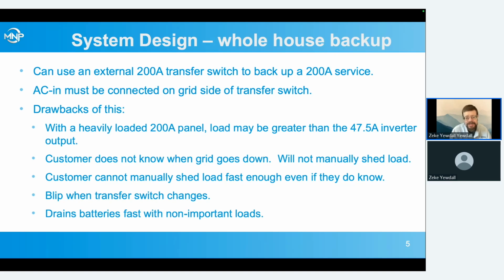But then the issue is the customer doesn't know when the grid goes down. A lot of them will say, I'll just manually shed my heavy loads if the grid goes down, so I'll turn off the air conditioner and the jacuzzi. But if you've got whole house backup, they don't know that the grid went down. I mean, yeah, they can go look at the lights on the inverter or pull up their app, but they don't get a notification like, oh, all of a sudden the lights all went out, the grid must have gone down.